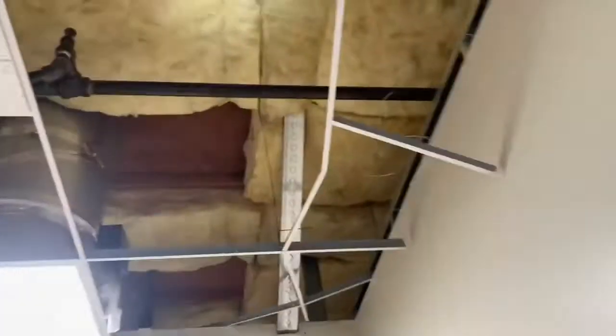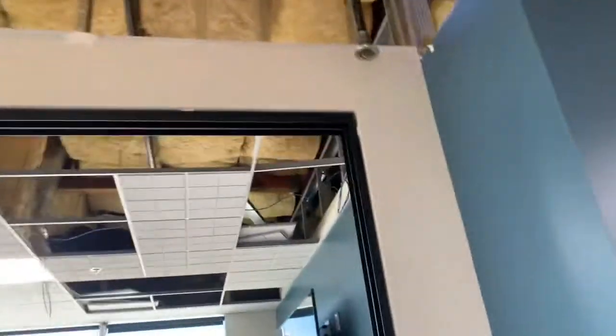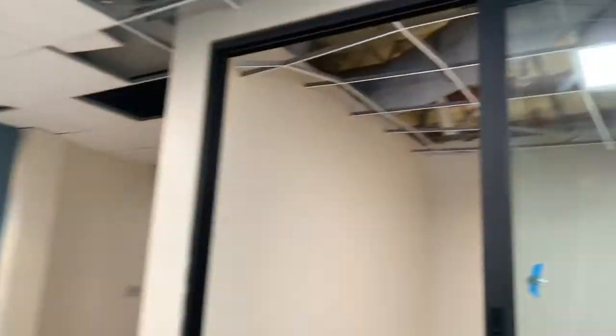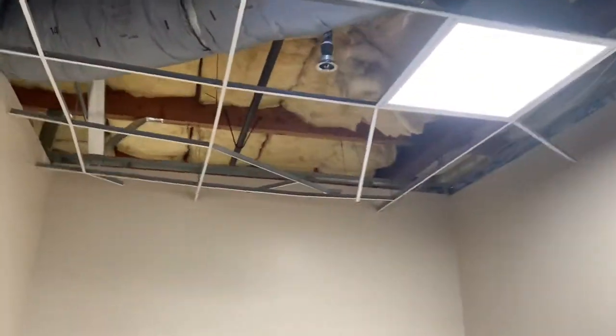I added these two heads — just adding, not center tile or anything. Small room rule, and I moved this one. Four inches off the wall. Added these two, relocate relocate. Beautiful — this is all dry. Added that one, fixed these two. Beautiful.